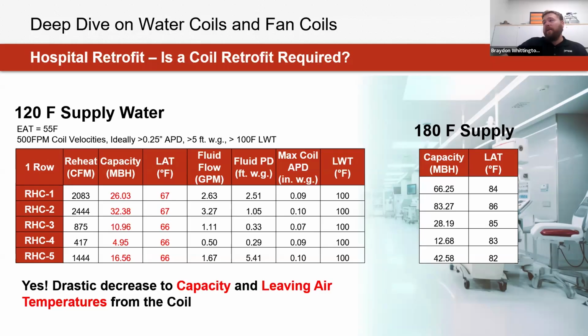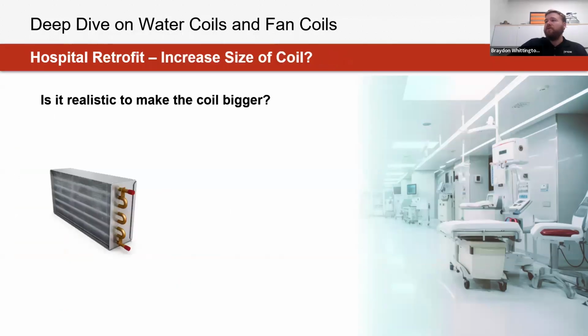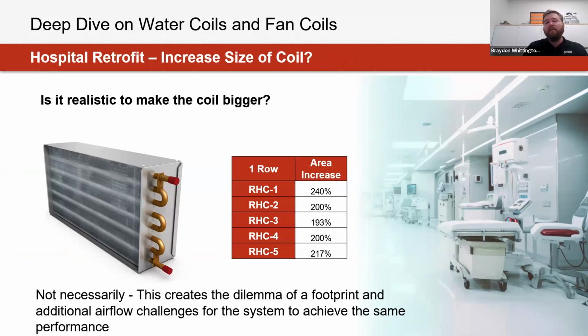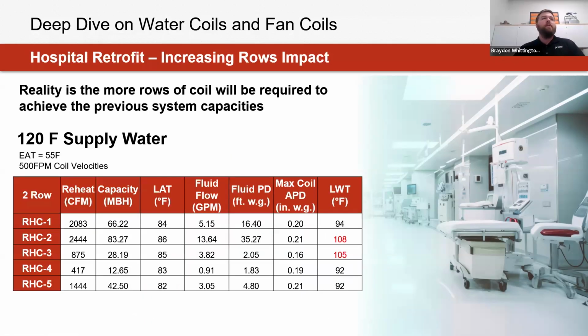All good points there. Yeah, I think a really common one, we'll go through some different examples of some questions that people might bring up there too, but appreciate your response there, Tom, and also Heidi there too, is first, is it realistic to make that coil bigger? Well, no, not necessarily, because then that really creates the dilemma for us, both from a footprint perspective, but then as we increase that coil, the amount of additional airflow that we're needing to provide to that same coil. So as you see here, for those same reheat coils, much more drastic increase, or nearly double the size of the same coil of what would be required to achieve that same performance there. Sorry, a little bit of a tongue twister.